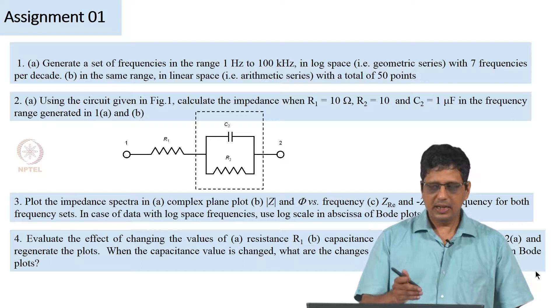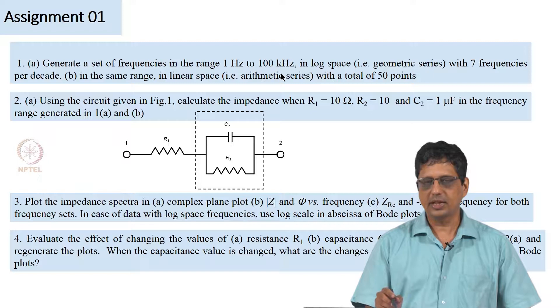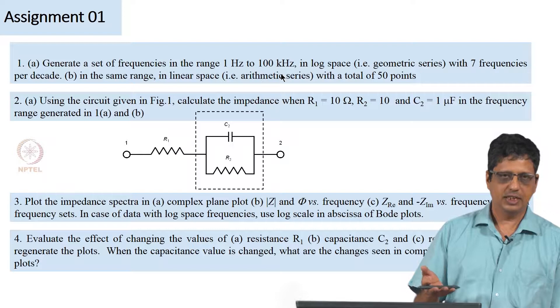So for that, I have split it into multiple questions. First part is to just generate a log space or geometric series frequencies from a minimum value of 1 hertz to maximum of 100 kilohertz, and typically we give 7 frequencies per decade. So I have given that number. At the minimum, you need 5 frequencies per decade. If you can get 10 frequencies per decade, it is well and good.